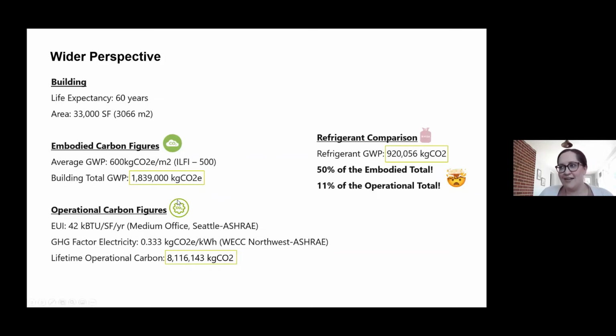Then if we go to the other camp of people who say refrigeration has to do with the operational carbon because it is your cooling fuel, let's look at this EUI, pretending this is a medium-sized office in Seattle. It's about 42 kBTUs per square foot per year. The GHG factor for electricity in Seattle is 0.33. The lifetime operational carbon for that building over the 60 years is about 8 million. That's still 11% of the operational total. So this is still a huge piece of the pie that has not historically been included, but this number can literally go to 0. So it's a great first place for us to start off with the MEP 2040 challenge, knowing that we can reduce this number down to 0, and we should.